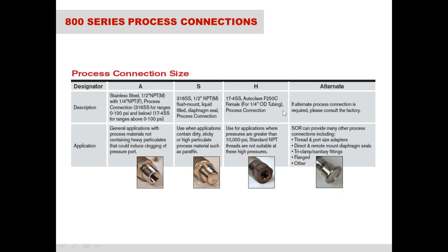We also have the H port. This H port is used and required for any process pressures above 10,000 psi. This is because normal NPT threads won't be able to hold or seal that pressure effectively. So you have to go to an autoclave fitting for those higher pressures. And then if one of those three options is not suitable, we can also do all sorts of different options on special requests, whether it's threaded ports, different types and sizes of threads and so on, or direct remote mount diaphragm seals, tri-clamp sanitary fittings, a flange, and then many other options that we can do.